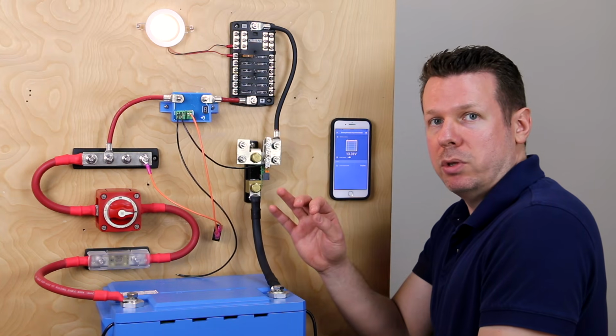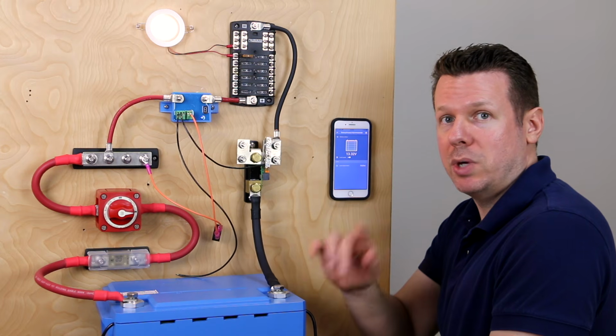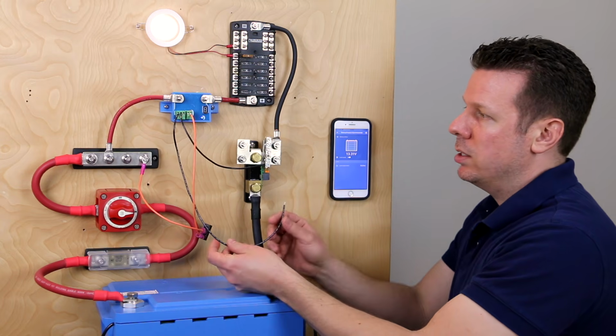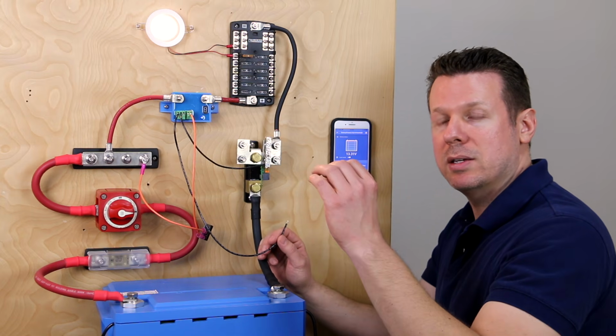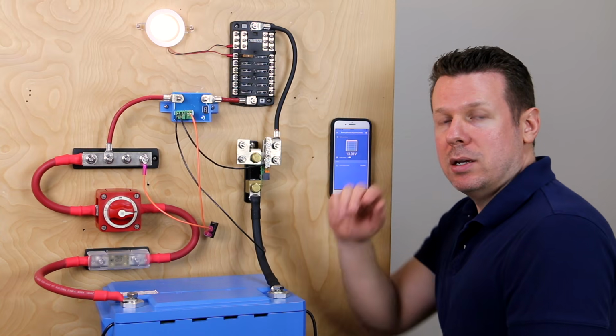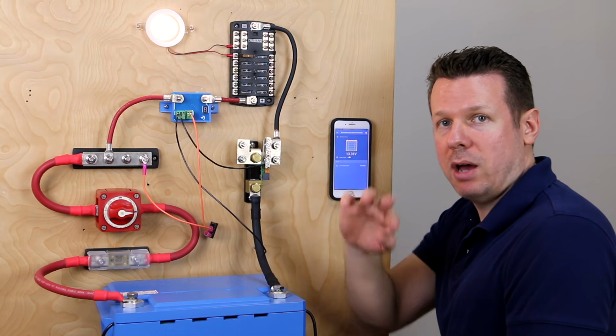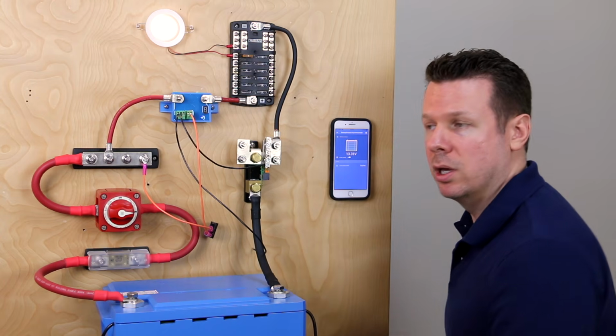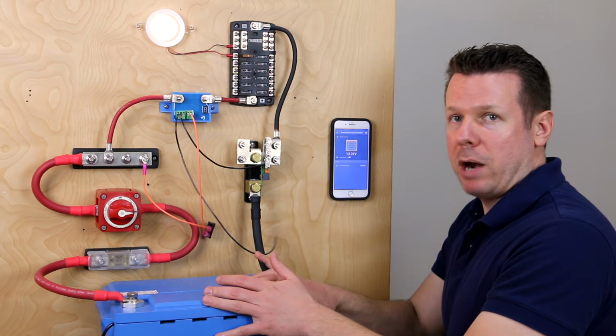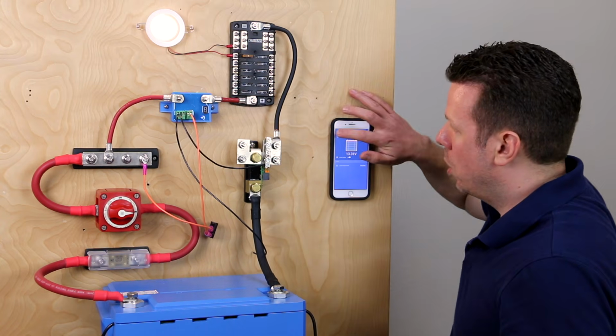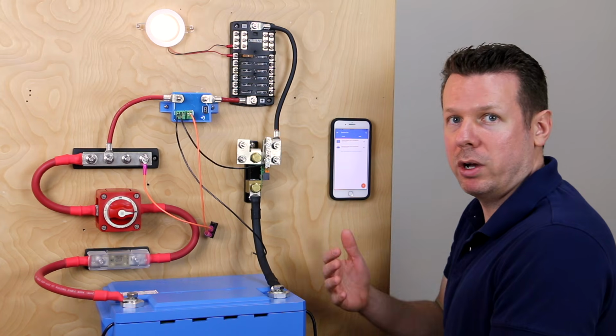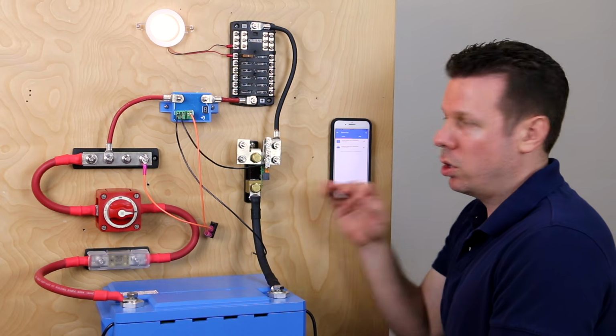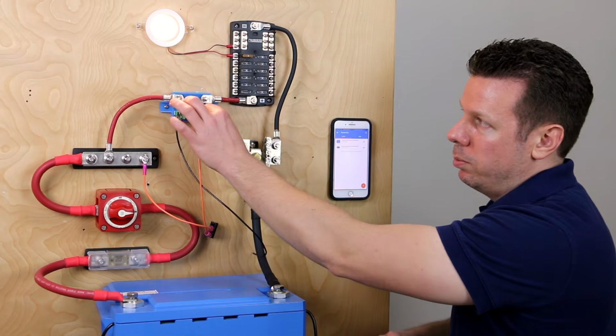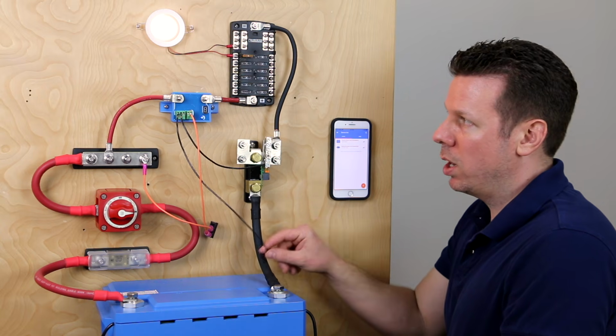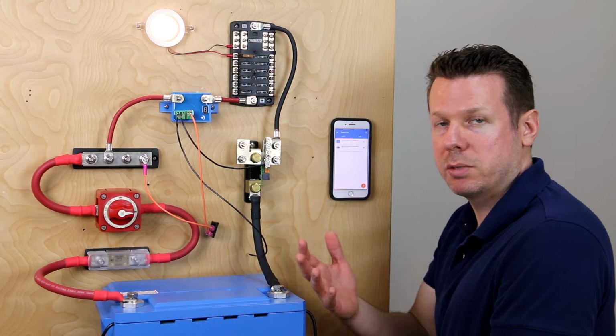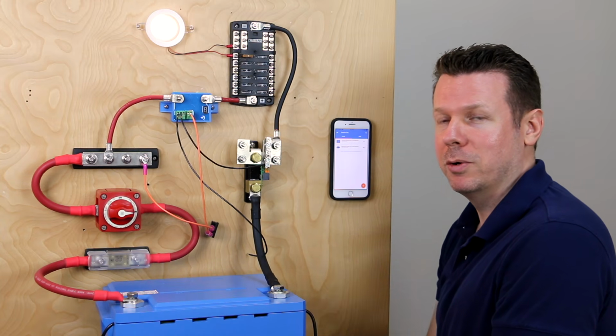If you get a Bluetooth edition, a smart BatteryProtect, and you want to disable the Bluetooth, you can do that with the old school programming wire. And remember earlier we had mode A and mode C. There is also a mode F and a mode H, and when you set it to H and F, that will turn the Bluetooth on and off. It's in the instructions. Let's say your batteries are putting out Bluetooth, solar, your battery monitor, and you go into the app and you just have a list that's very, very long, and you're not really using the Bluetooth capability for this unit - you can turn it off so it eliminates it from the list by putting it into H mode with the programming wire, and it will kill the Bluetooth signal. You can turn the Bluetooth signal back on by putting it into F mode. So I hope that made sense.